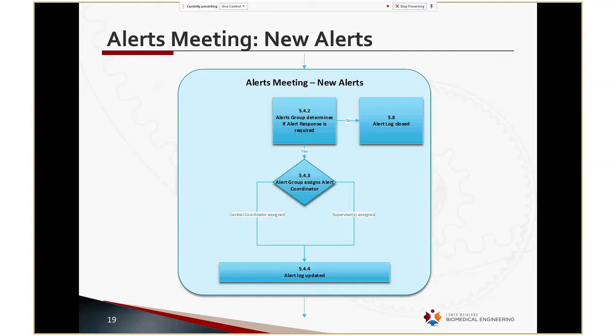And so what we do is we start with the alerts that have entered our process where we haven't found any devices that are affected, and then we will ask everybody on the line, so all the supervisors or their delegates, if they're aware of those devices within the hospital. And so we've actually seen quite a positive improvement with that extra step. In the pilot phase, we caught multiple alerts where the DBM team hadn't found anything in the database, but the healthcare institution that we service was actually affected. So we do that second pass.